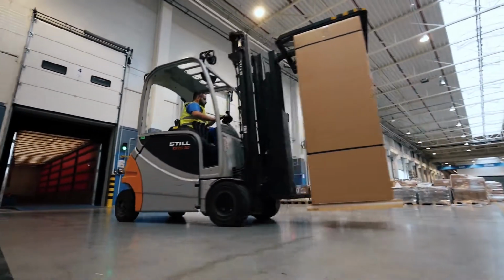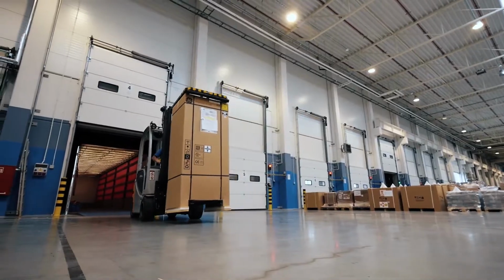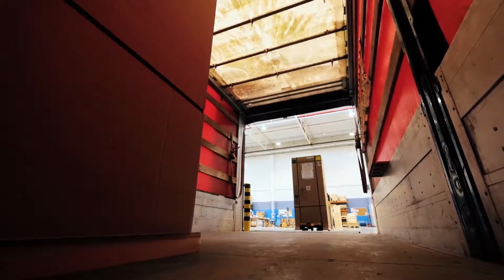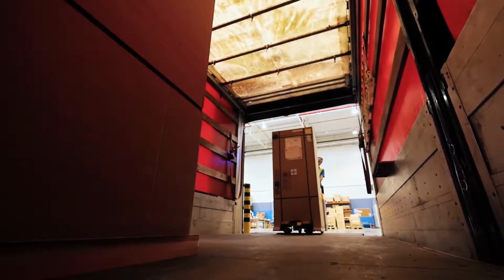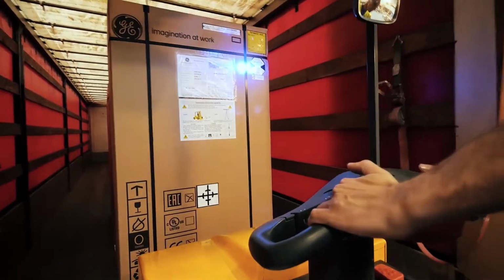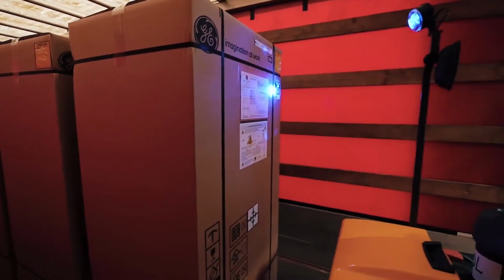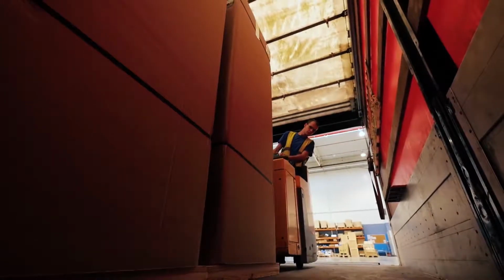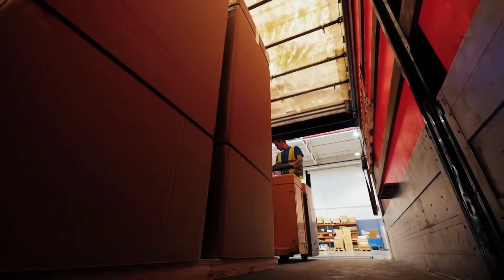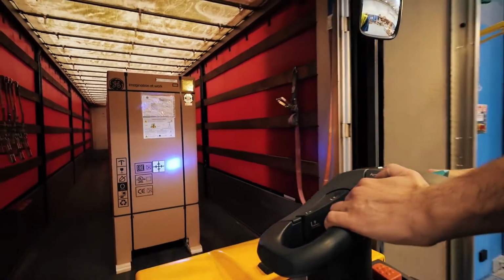Transporting is an important stage. The weight of a single UPS unit can be up to 800 kilograms. The center of gravity is in the middle. If you tilt the UPS more than 30 degrees, it may fall. In this case, a unit is sent back to the factory where it should pass all the tests again to prove its operational readiness.